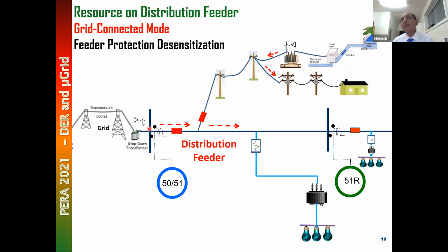A very important thing I want you to observe, although I will not talk in detail about it, this is a topic of transmission microgrid, I am not going to touch it, but I want you to see this. A typical distribution transformer connection is delta on the high side, on the transmission side, and Y solid grounded on the distribution side. Why? Because this transformer provides effective grounding. The distribution systems are effectively grounded, at least in North America and most parts of India too. So an effectively grounded system requires the transformer to be delta on the high side and Y solid grounded on the low voltage side.